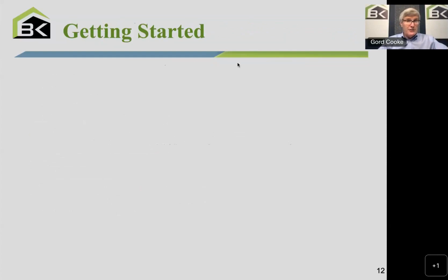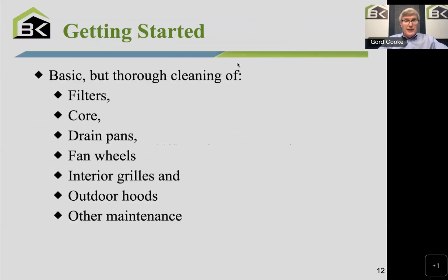And let's think about getting started. In terms of today's session, it's really about a thorough cleaning of the filters, and we'll go through each one of these: the core, the drain pans, fan wheels in some cases, interior grills, the ones on the wall in the bathrooms or the kitchen, or the supply ducts in the bedrooms. We want to clean the outdoor hoods, and there may be some other maintenance that I kind of alluded to as we went.